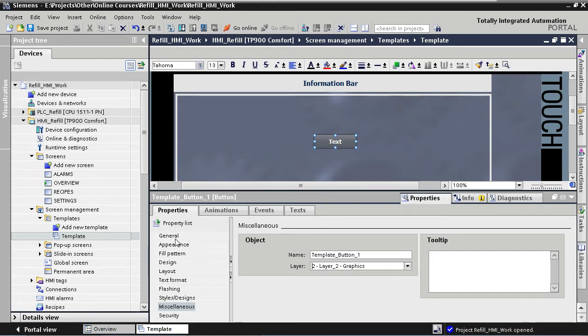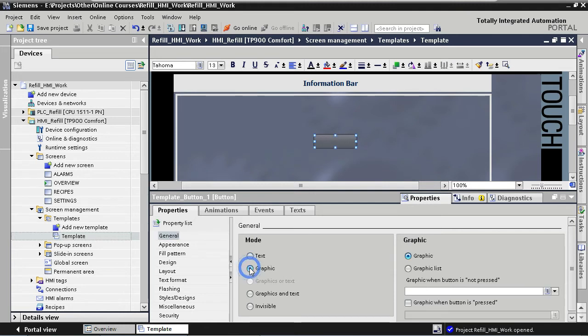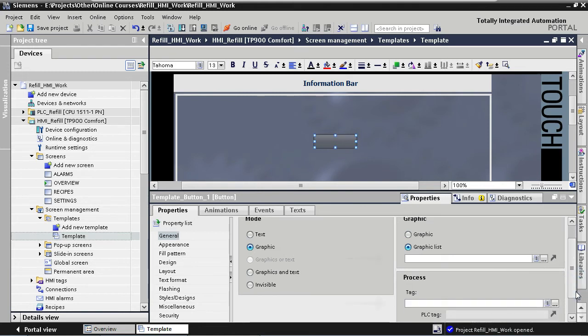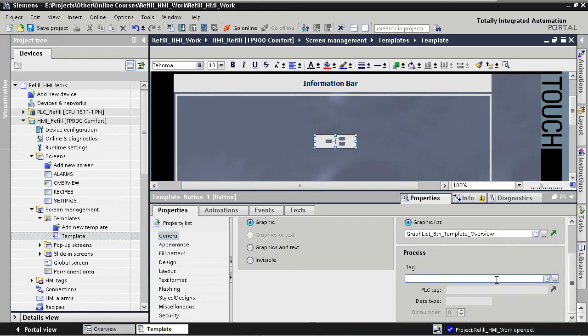To change the graphic settings of our button, we go to General. Instead of using the default text, we are going to use a graphic list. By using a graphic list we'll be able to show a different graphic depending on the state of a tag. We assign a graphic list by selecting Graphic Mode on the left and then Graphic List on the right. We need to assign a graphic list and a tag — and we've already created these in our previous steps. So for the graphic list we select our Overview Graphic List and we select the corresponding tag. The button has now taken on the zero-value, or inactive, graphic from our graphic list.